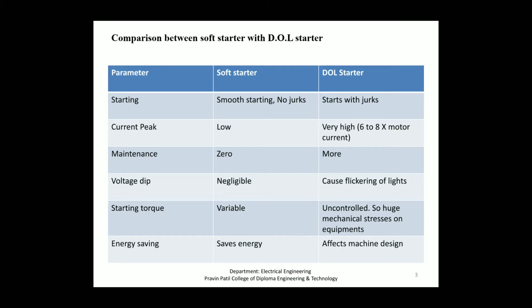Then what is the comparison between the soft starter and DOL starter? The first point is starting. Soft starter gives smooth starting, no jerks, meaning at the time of starting the motor starts smoothly without any jerk. But DOL starter starts with jerks. Then peak current, that is the starting current. In soft starter the starting current is low, but in DOL starter it is very high, that is 6 to 8 times the motor current, meaning normal current.